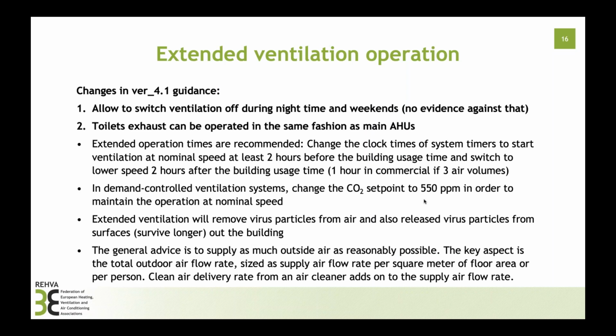So to go through some of these recommendations, what REHVA has basically recommended: in the first guidance last year it was set that ventilation should operate all the time, day and night, 7 days, 24 hours and so on. But this has been changed because there is actually no evidence, and we know now that this virus is only 3 hours active in the air, so basically no need to operate the ventilation during the night time. And now it's recommended that the extended operation time is 2 hours before and 2 hours after building occupancy, and in commercial buildings where you can expect higher air change rates, so if the three air volumes will be ventilated in 1 hour, then this 1 hour is enough.